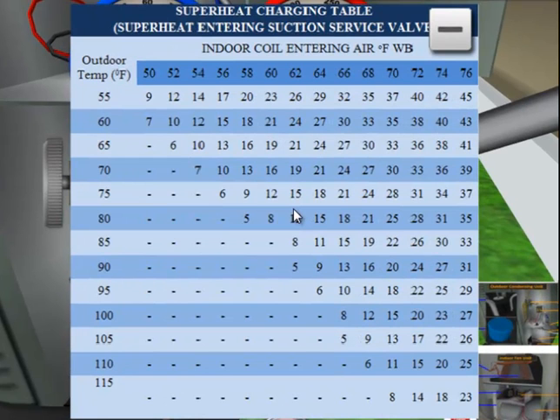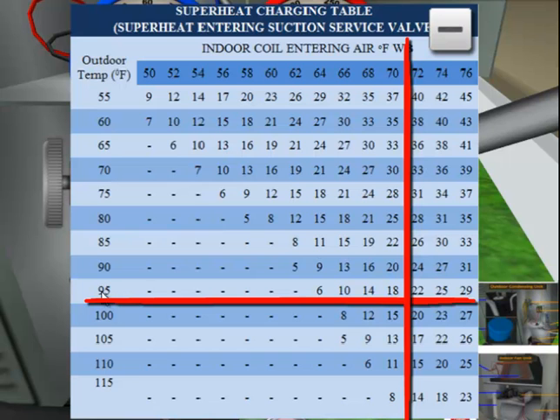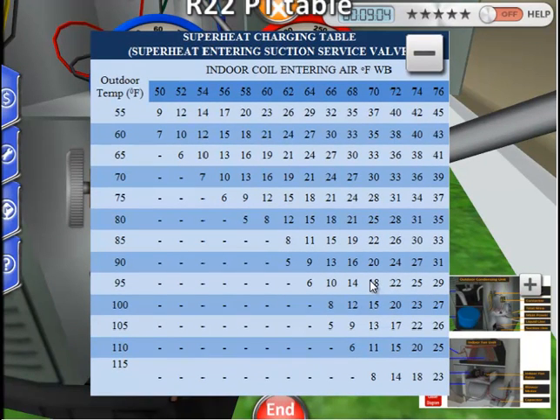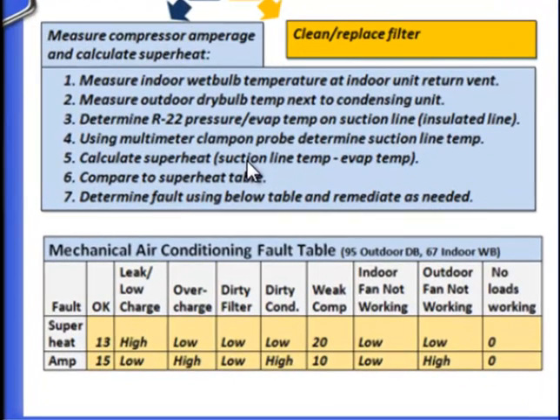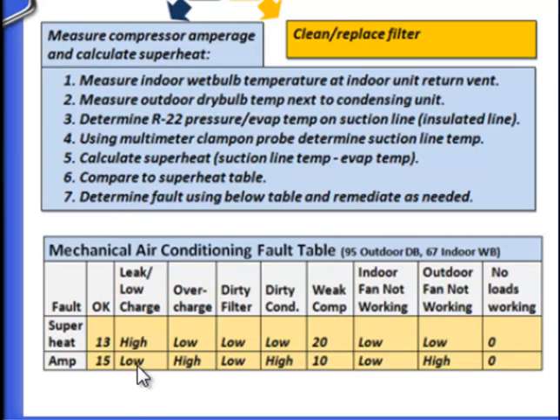You can toggle between these two charts. We have an outdoor dry bulb temperature of 95 degrees and an indoor wet bulb temperature of 70 degrees. This means we should have only about 18 degrees of superheat. Our level of 49 degrees of superheat is too much and indicates a problem. When we look at the table on the bottom of the troubleshooting chart, we can identify the probable cause in the second column as leak or low charge, because we have high superheat and a low compressor amperage of 11 amps instead of 15. Before we add refrigerant to fix the problem, we'll first want to do a leak test on both the outdoor and indoor lines.